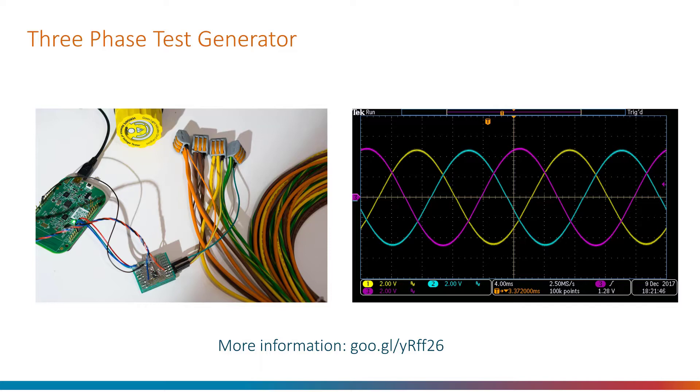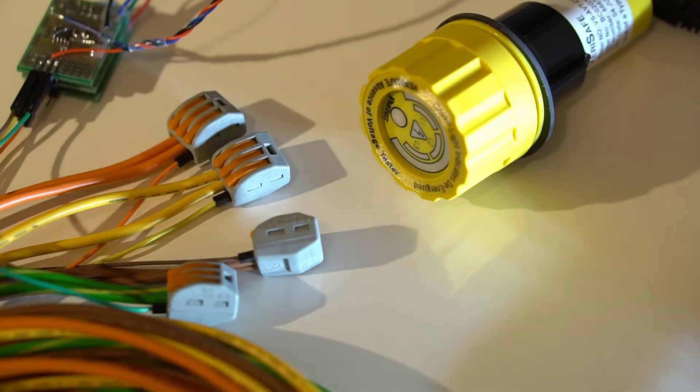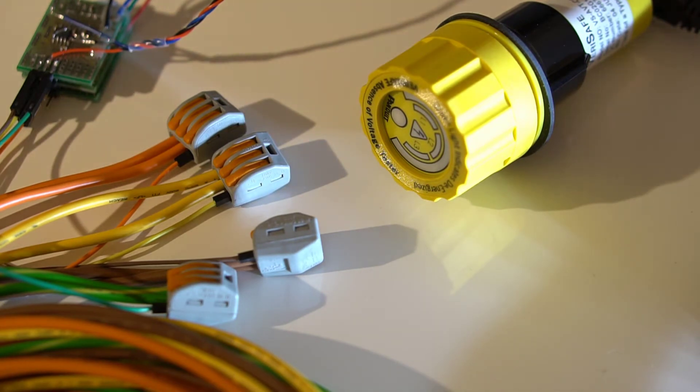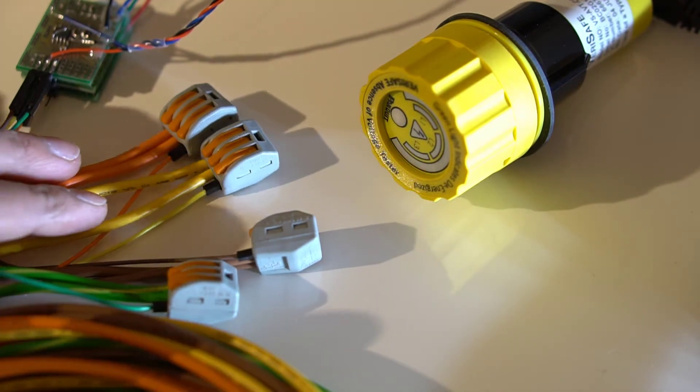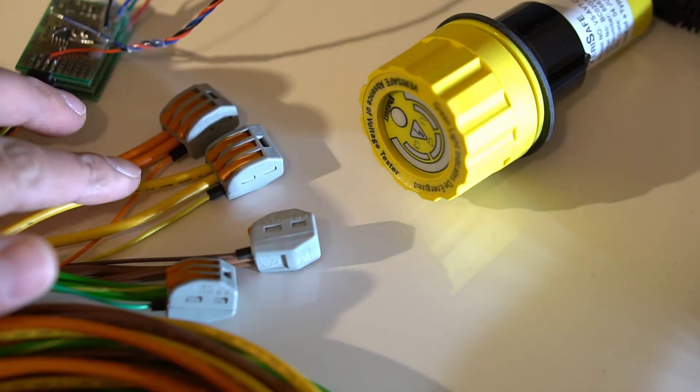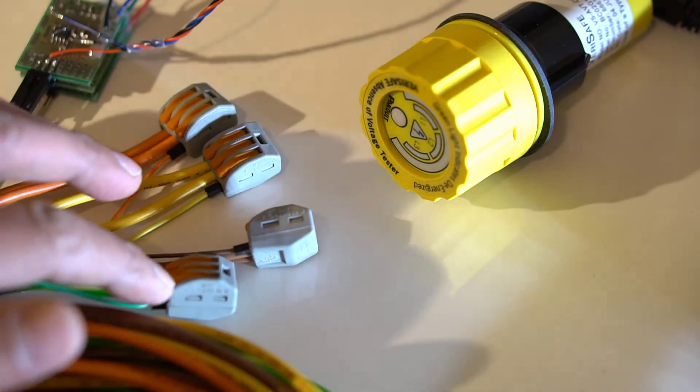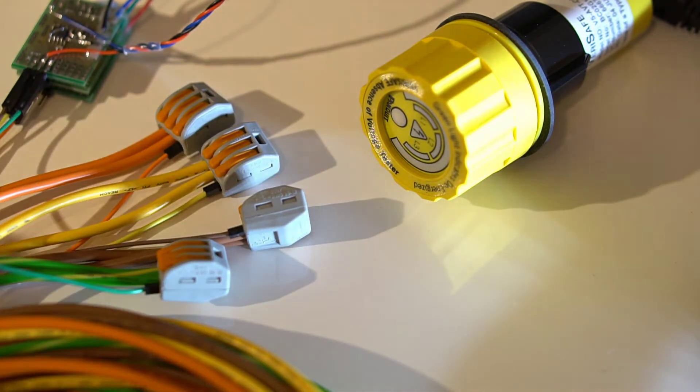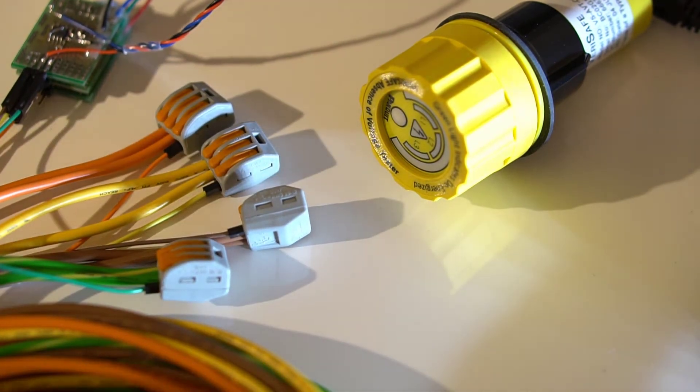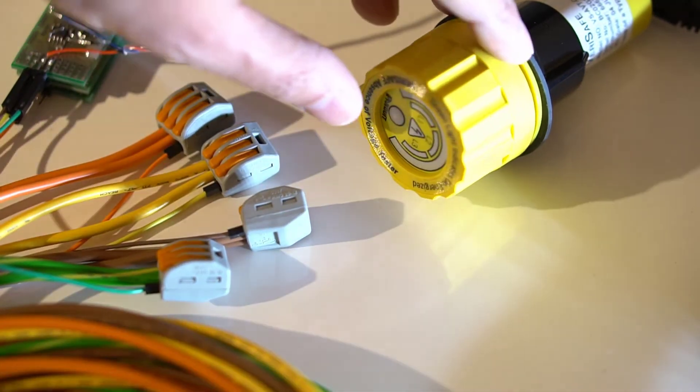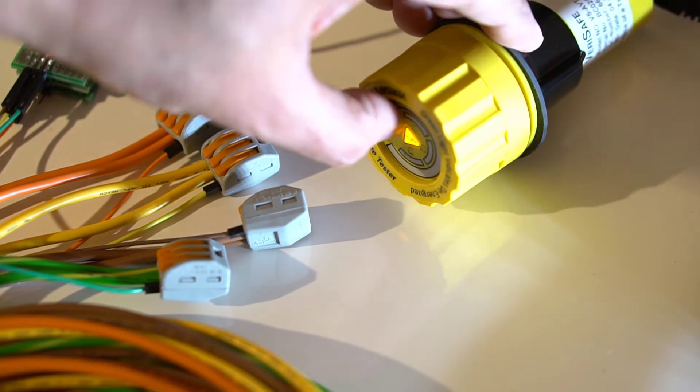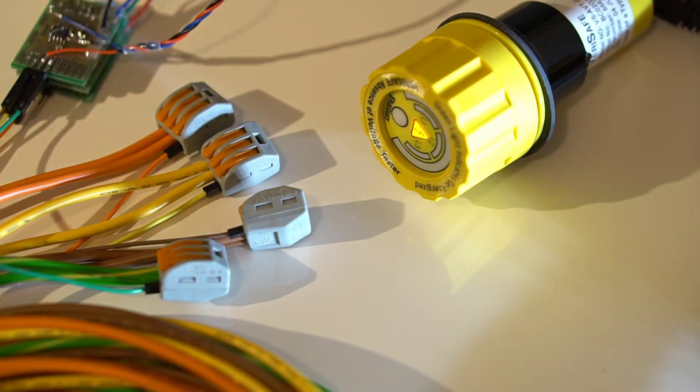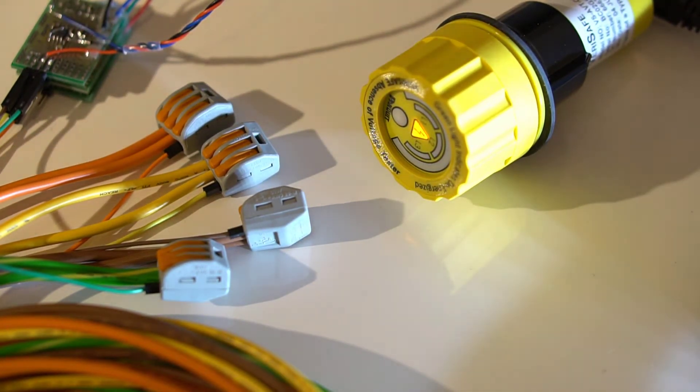To perform the test, the three-phase system was turned on so that all three phases were live. The VeriSafe system uses two wires for each phase, basically for redundancy and also to perform its self-test. When I press the button, the warning triangle flashes while performing the test, and then it stays lit for five seconds.